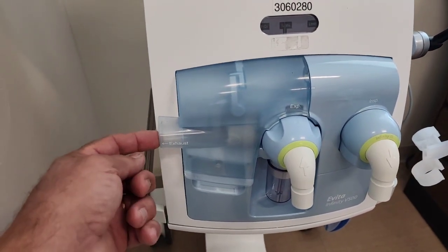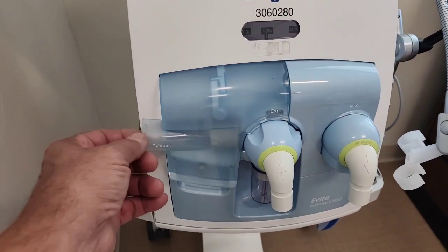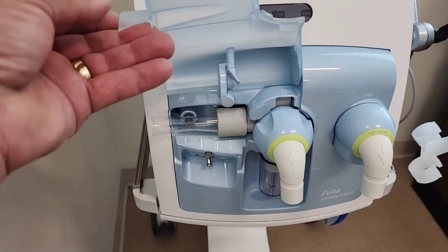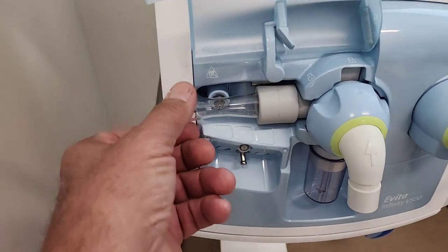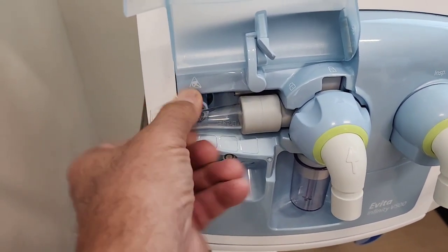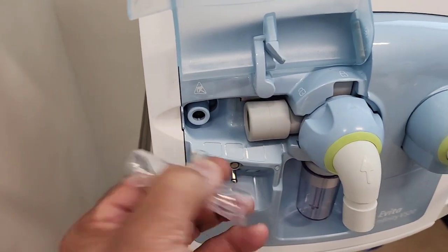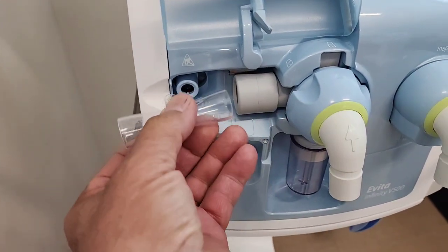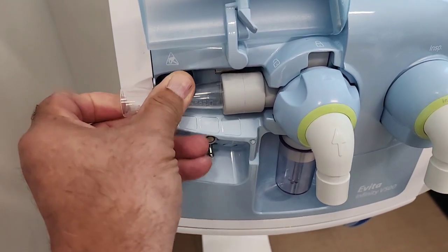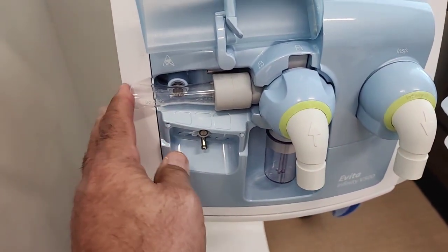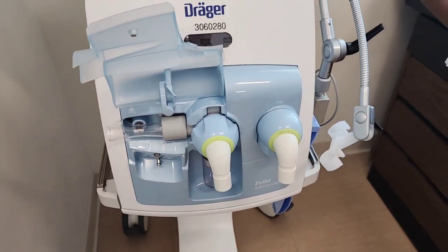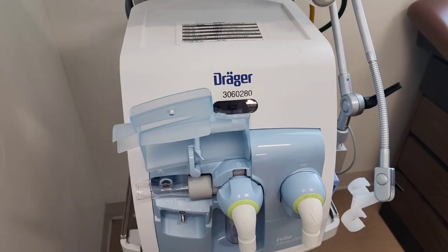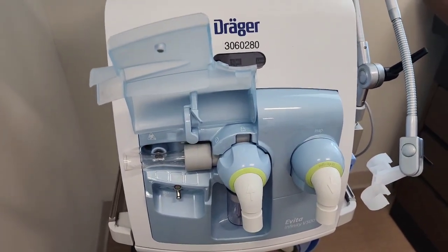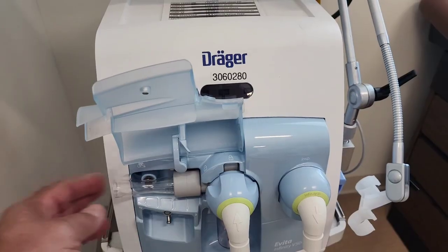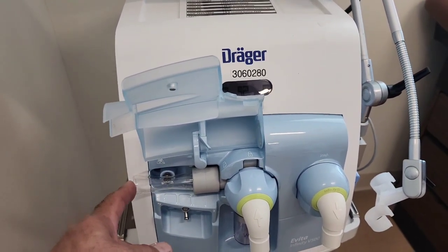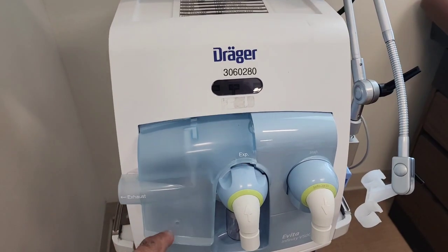And behind here, this is the exhaust. This is where it'll kind of empty out. But there, behind here, let me open it up, there is a flow sensor. This here is a flow sensor, and it can be removed. It's a flow sensor. Okay. I'm going to put it back in. Okay, so this is measuring exhalation after the breath has been delivered by the ventilator. It's going to come back to the ventilator and be exhausted here, and the flow sensor will measure that volume.